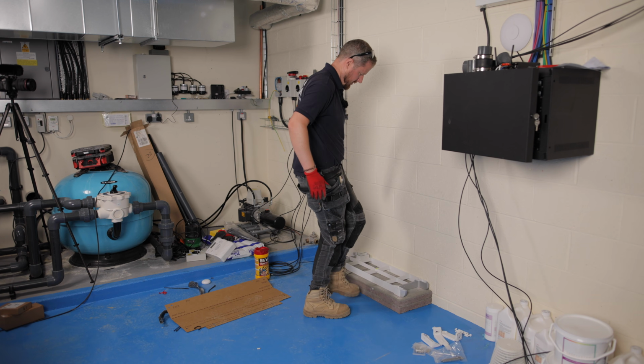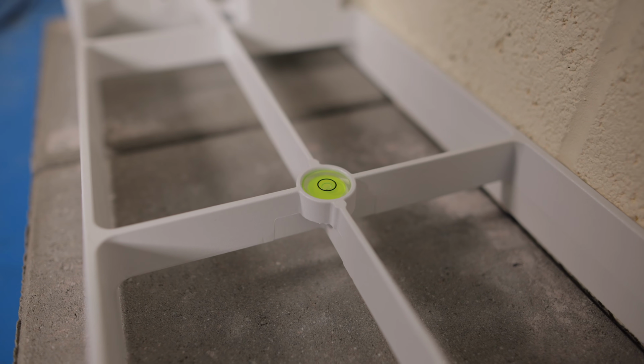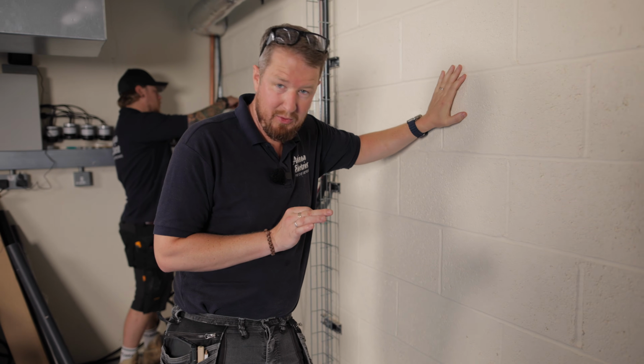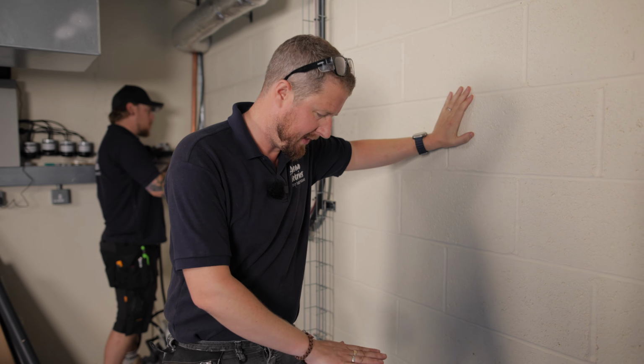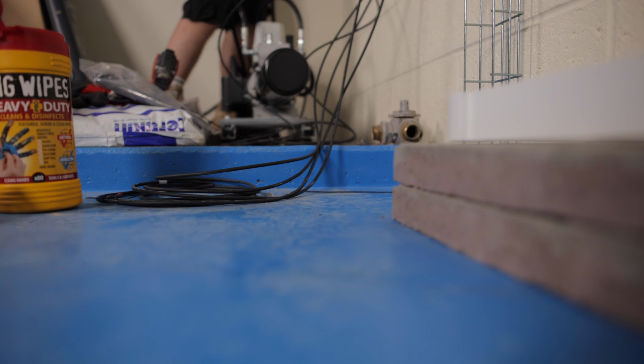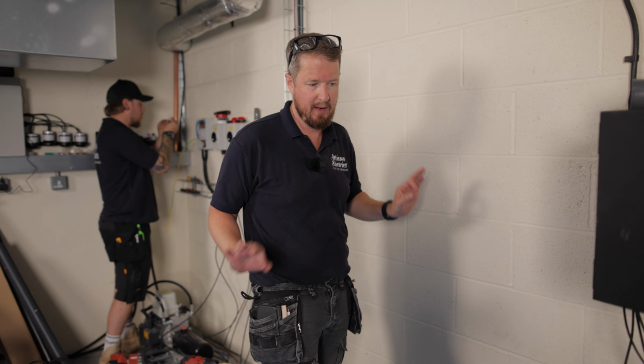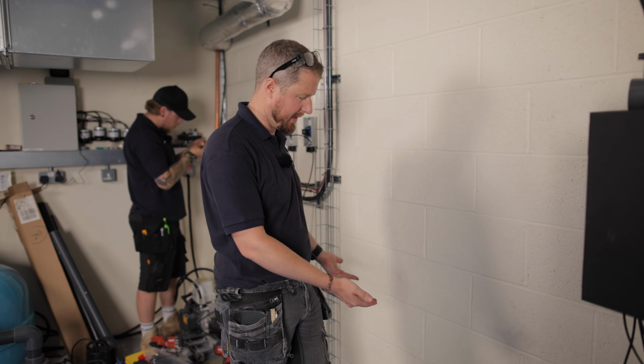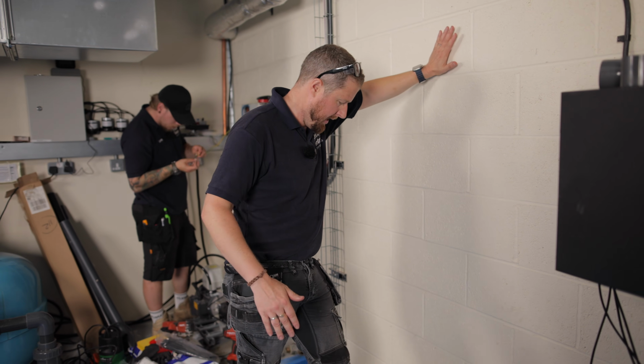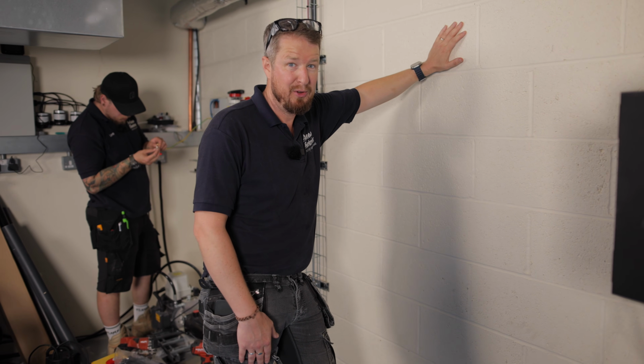So we've got 6 concrete blocks basically to lift this off the floor. It is bang on level, which is fantastic, and we lifted the metal base above the edge of this drip basin essentially, so it means that there's no chance of water actually getting to the bottom of the battery now. So now it's time to stack those modules.